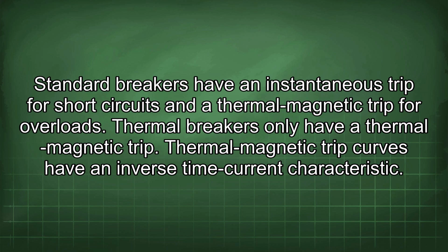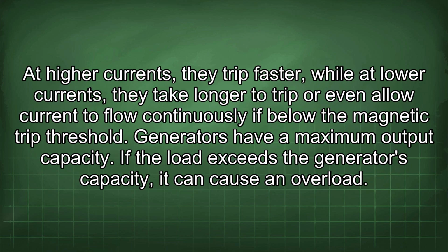Standard breakers have an instantaneous trip for short circuits and a thermal magnetic trip for overloads. Thermal breakers only have a thermal magnetic trip. Thermal magnetic trip curves have an inverse time current characteristic. At high currents, they trip faster, while at low currents, they take longer to trip or even allow current to flow continuously if below the magnetic trip threshold.